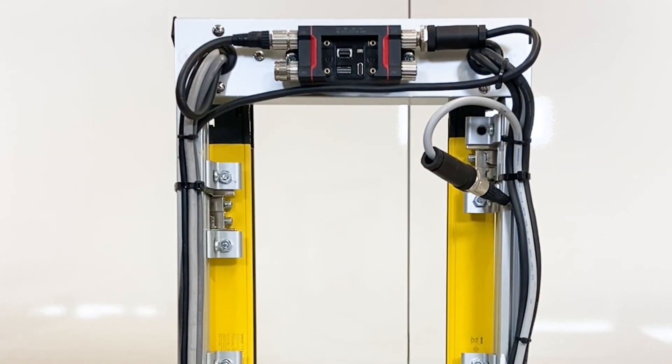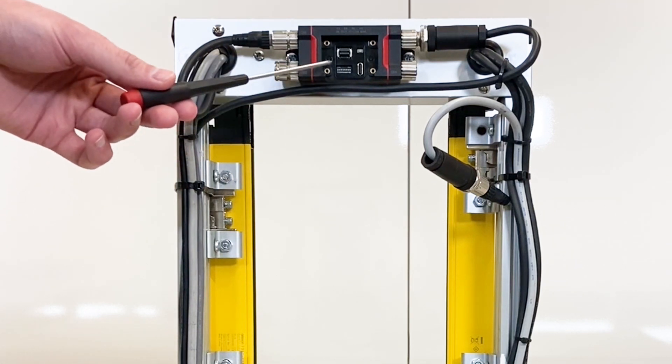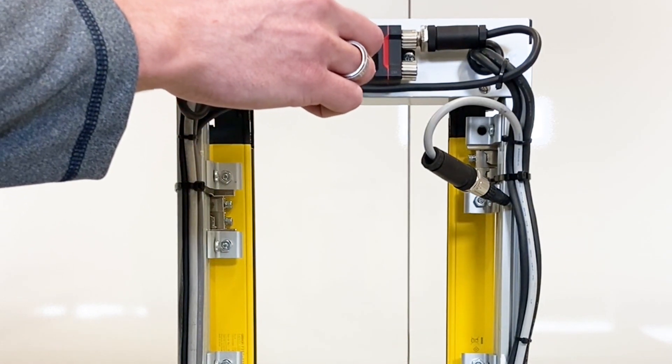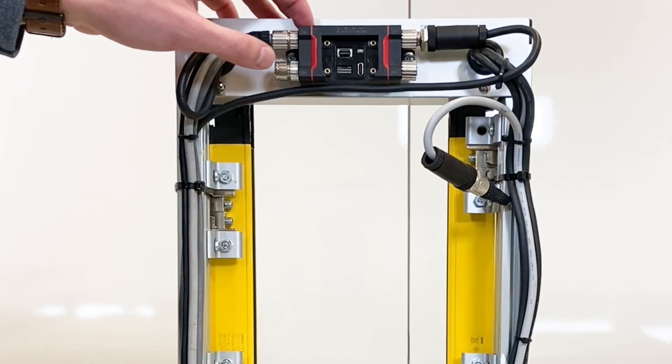Once removed, you will be able to see the DIP switches that you will need to program your safety light curtain. In order to program EDM, you're going to want to make sure DIP switch number 1, 2, and 3 are in the on position.